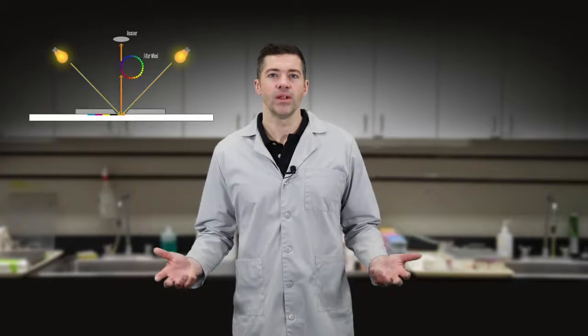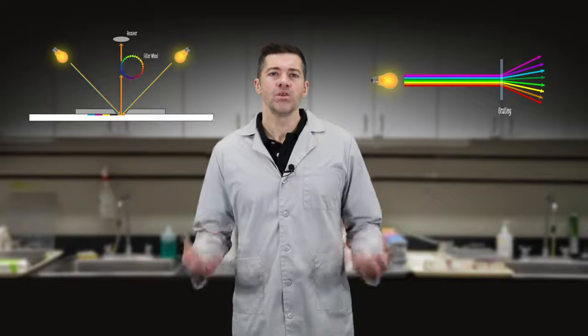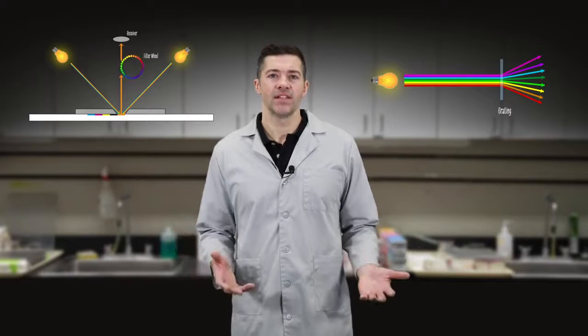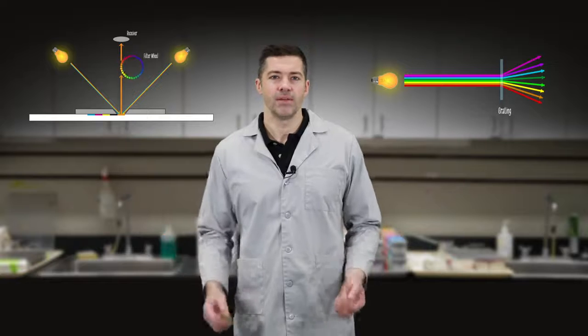This is typically achieved within an instrument using a spinning filter wheel of specially designed colors or a diffraction grating. The resulting measurement is the sample's reflectance curve with a varying wavelength from around 400 to 700 nanometers. From this, we can compare the curves of two samples to see if they are a match.